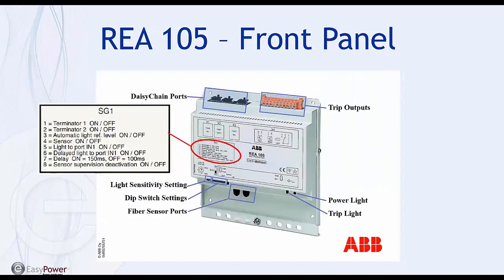Now we'll look at the REA 105 front panel, and you have your termination switches for terminating the last extension unit in the daisy chain. Backlight compensation, you can activate the sensor. Light to port input 1: you can use the light from input 1 to send back to the main unit. In that way it can act basically like an REA 103. Generally that application is not used.